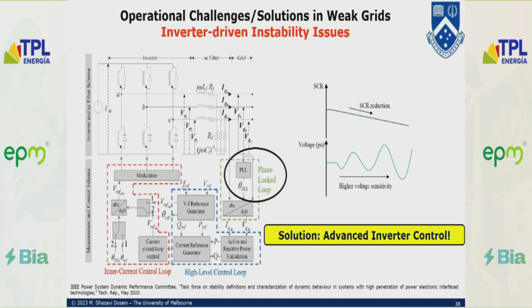Another important issue related to voltage is that in the distribution network, you want support from distribution for transmission network control and operation - multiple support, frequency control, voltage control. But if these inverters are in a weak distribution feeder, when they try to provide frequency response to the upstream network by changing active power, the system is so weak that the voltage goes wrong. This negative interaction between different services has to be considered in system operation of a renewable-rich power system.